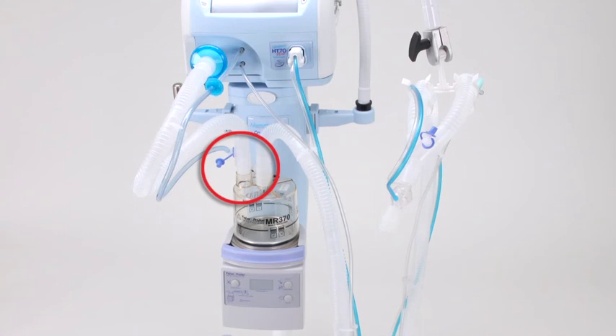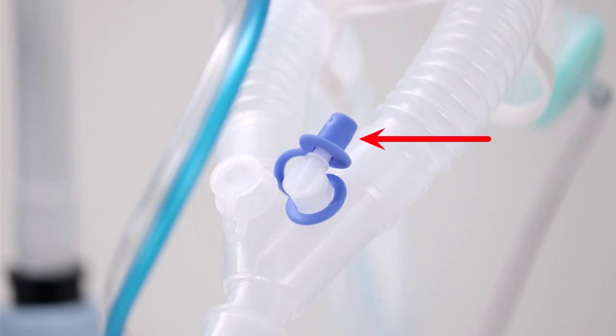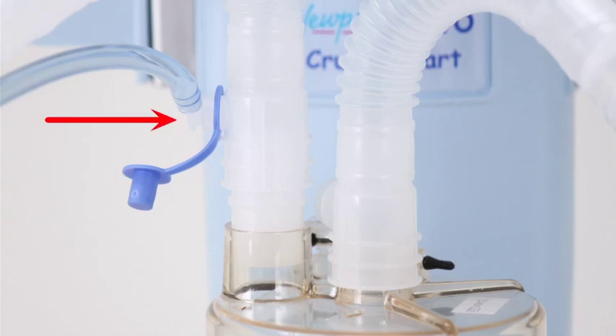In this situation, you are putting active humidity into the breathing circuit. In order to keep the pressure sensing line dry, you will need to connect it to the circuit on the dry side of the humidifier rather than connecting it to the Y connector where humidity is high. Disconnect the pressure sensing tubing from the Y connector, use the blue cap to close off that port, then connect the pressure tubing to the port provided at the end of the humidifier tubing.